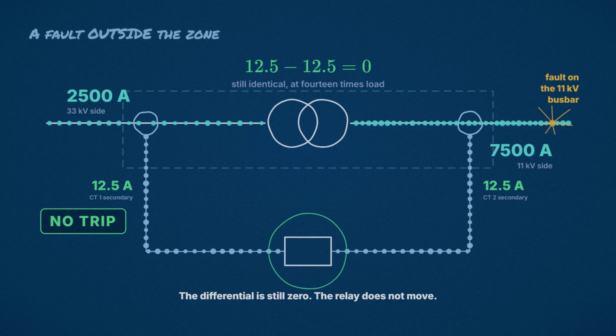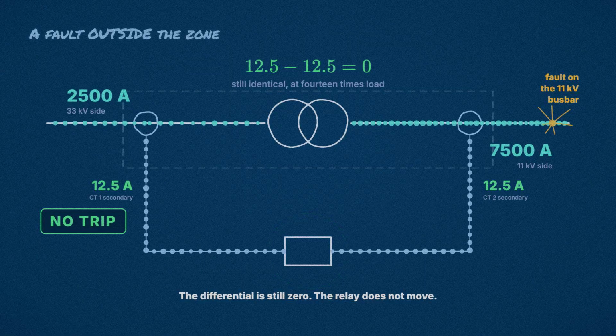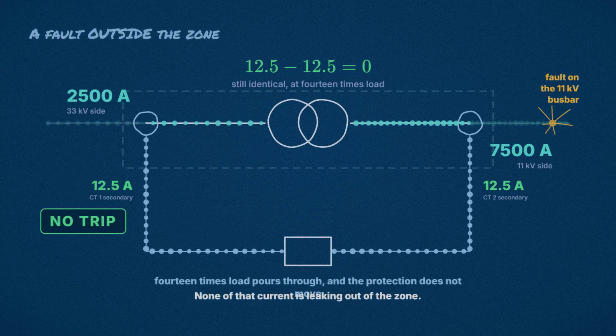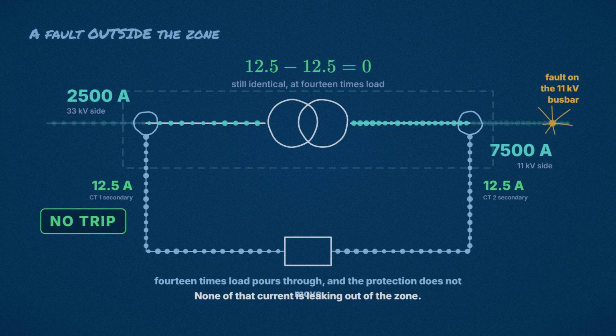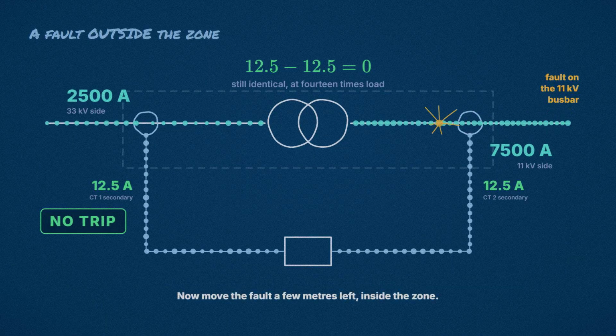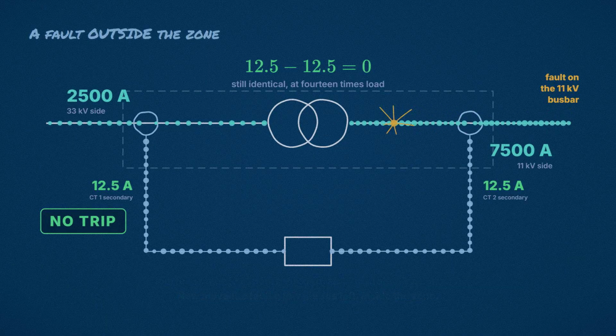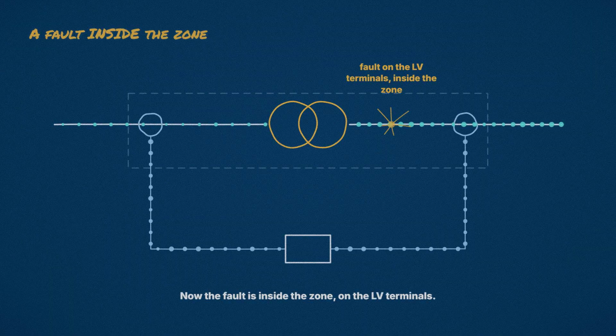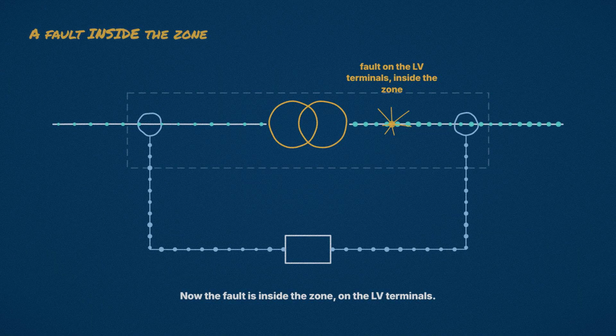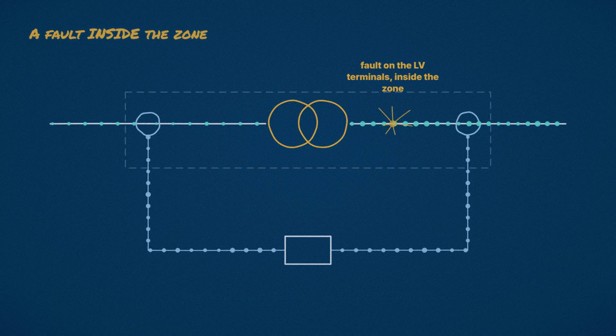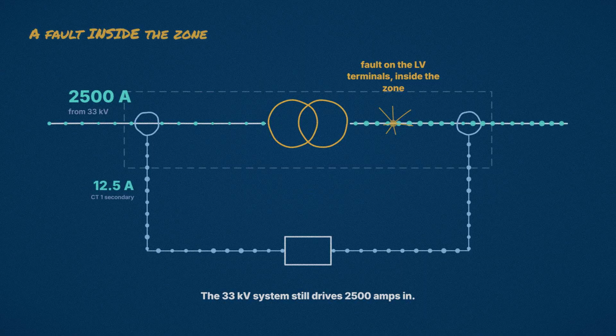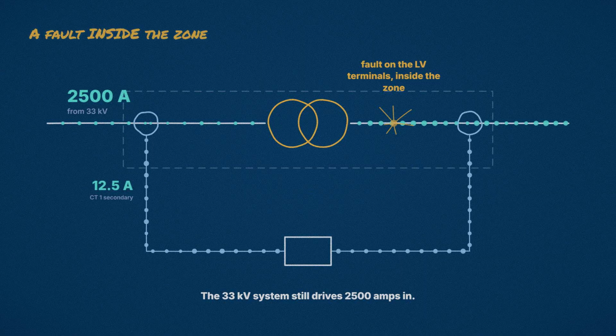That is the whole point. 14 times full load current is pouring through this transformer, and the protection stays perfectly still because none of it is leaking out. Now move that fault a few meters to the left inside the zone. Now the fault is inside the zone, on the low voltage terminals, between the two current transformers. The 33 kilovolt system still feeds it. 2,500 amps still flows in on the high voltage side.